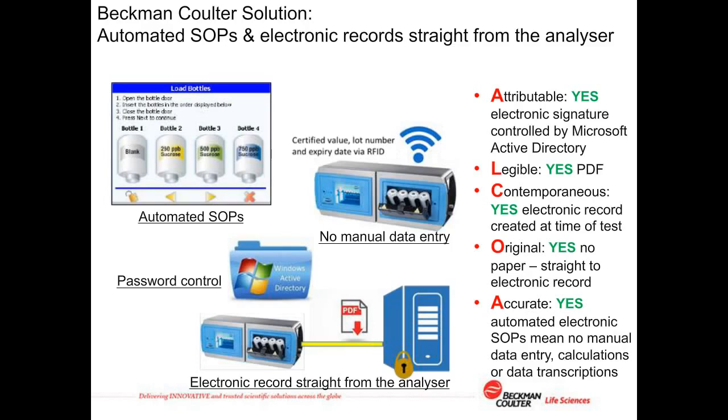Thank you. And I think you just answered this question, but I'll go ahead and ask it anyway. Does the Anatel keep the original record in the instrument memory, or is it removed upon exporting? Yeah, so there's two ways you can do this. The Anatel PAT700 does have username and password security on it in multiple levels. So you can apply the normal 21 CFR Part 11 security to the analyzer itself, should you wish to keep the record in the database inside the analyzer. But what I've seen a lot of people doing is that once they've exported the file electronically from the PAT700, to avoid any confusion over where the last file is and which one it is, and is it in the analyzer or is it in the secure archive, they set the analyzer to automatically delete the file. So you can program it so it automatically exports the PDF files at a set time every day and goes back in and wipes the files from the analyzer. So it just removes that ambiguity as to where the final record is kept.